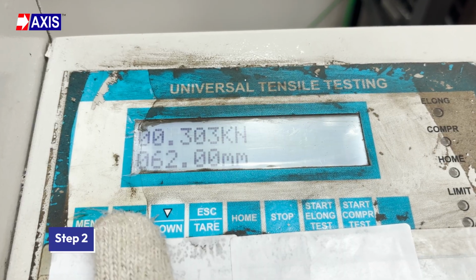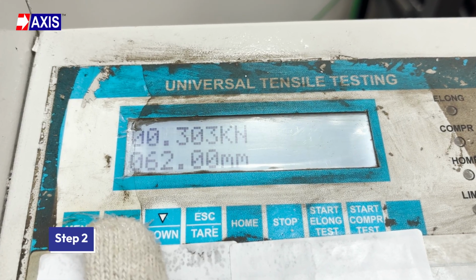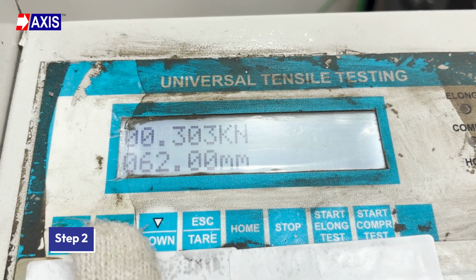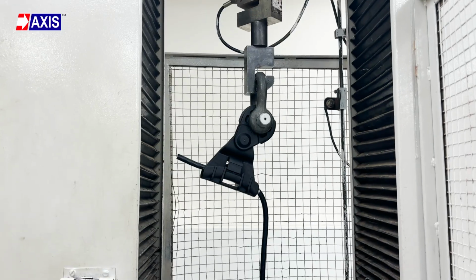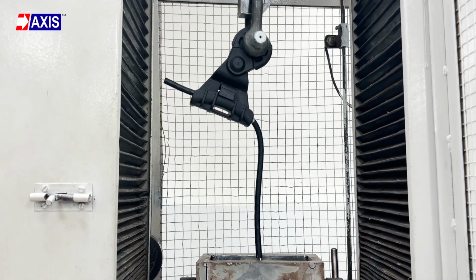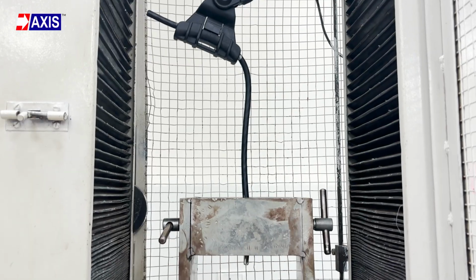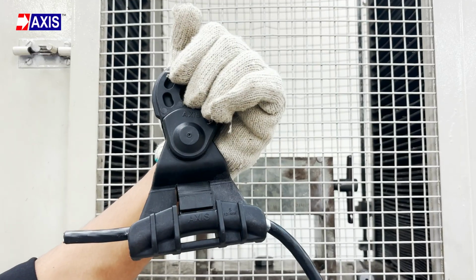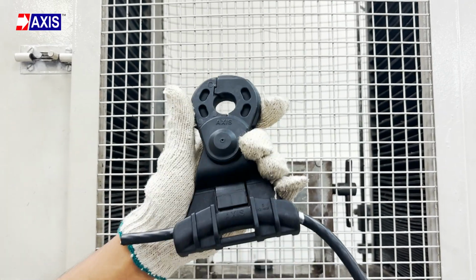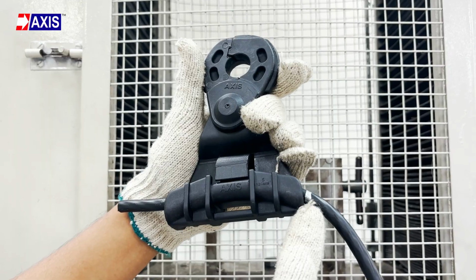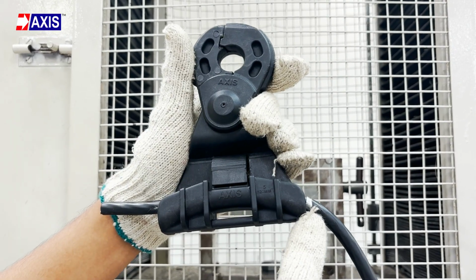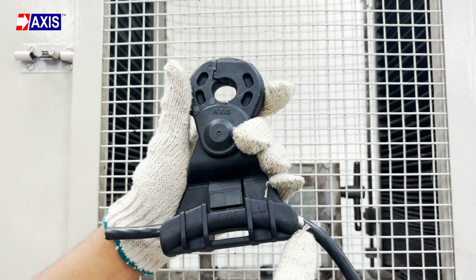Step 2. Gradually apply a longitudinal load to the neutral messenger and increase it to 300 newtons. The total slip of the neutral messenger cable does not exceed 2 mm. The clamp passes if no damage occurs. No component of the clamp shall be dislodged. As you can see, the cable has not slipped from the clamp's marking. This shows it has passed the test and the gripping is perfect.